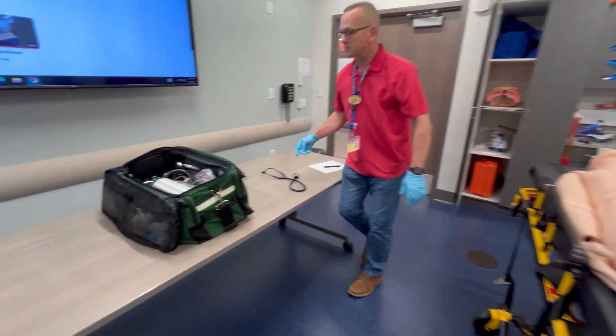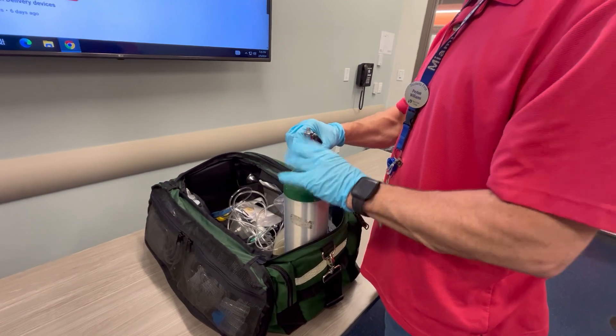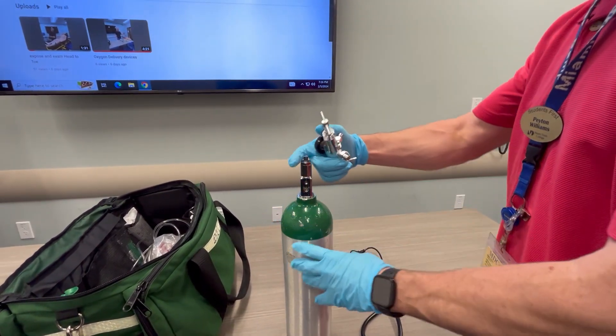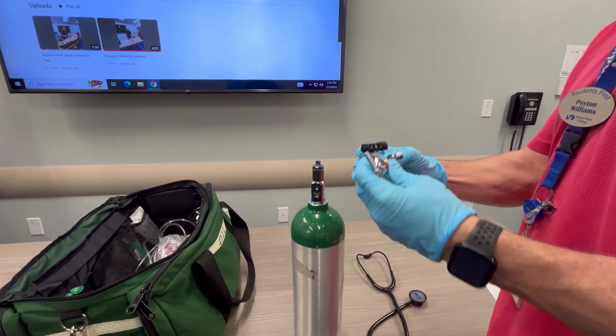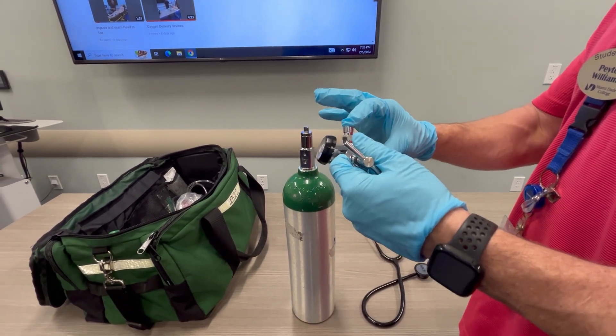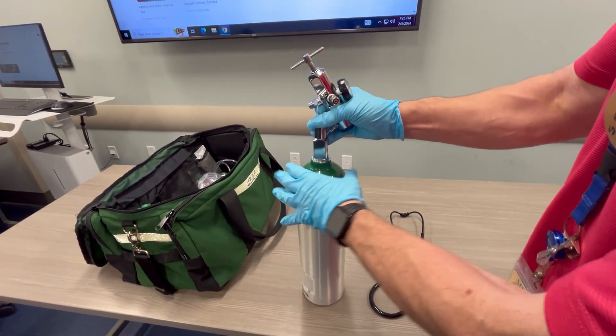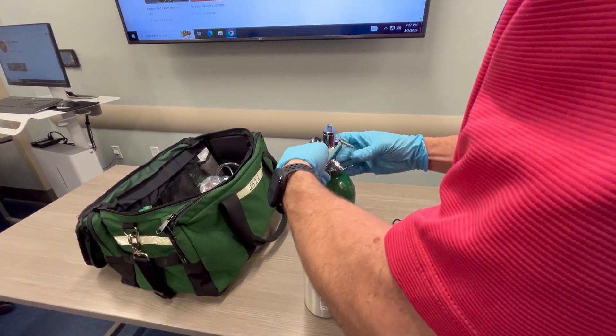I'm going to assemble the oxygen tank. Checking to make sure it's not damaged, that it's a green oxygen tank, and checking the hydrostatic test date within five years. Checking the regulator — the flow meter, Christmas tree, two high-pressure valves, the gauge, regulator gasket, and T-screw — making sure all parts are present and the pin index system is aligned.